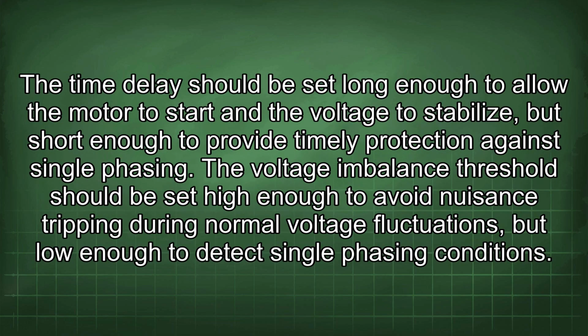The time delay should be set long enough to allow the motor to start and the voltage to stabilize, but short enough to provide timely protection against single phasing. The voltage imbalance threshold should be set high enough to avoid nuisance tripping during normal voltage fluctuations, but low enough to detect single phasing conditions.